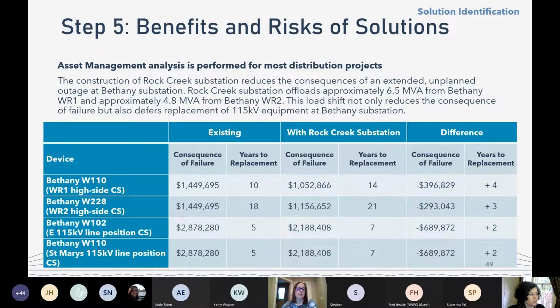We perform asset management analysis for most distribution projects. I say most because when we have things like large load additions, those are considered must-dos for us - we have to do something to serve that load. But for things like offloading an existing substation with a new substation, or replacing assets, we look at the reduction in risk and consequence and years to replacement - how many extra years you have as a result of this substation. Consequence of failure is really the impacts that the failure has on our customers, our employees, and our assets.